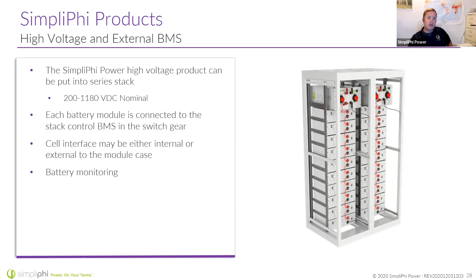So the takeaway here is that a digital battery management system isn't necessarily any better than a battery that has an analog battery management system. Imagine you come out to a home that has some old Xantrex equipment. As long as that older equipment can meet the set points we want to see, there's no reason you need a digital battery management system, because there's no way that old Xantrex is even going to be able to talk to that piece of equipment. So if you've got a lead acid battery replacement customer, sell them the standard Phi batteries.